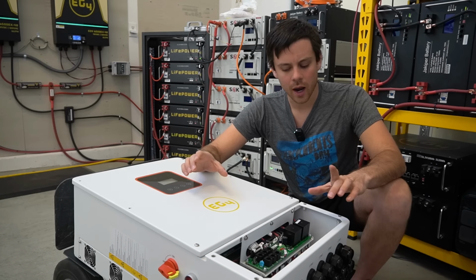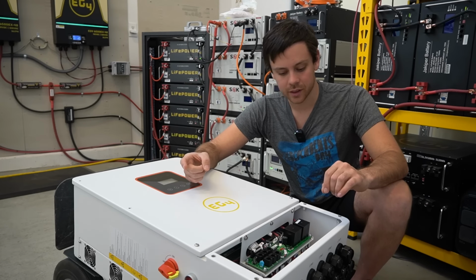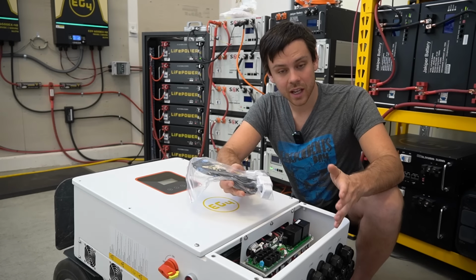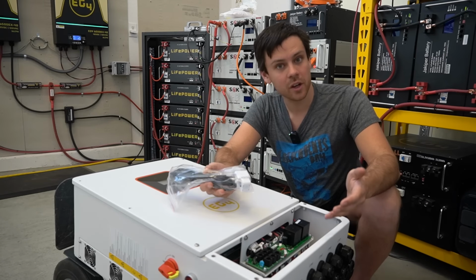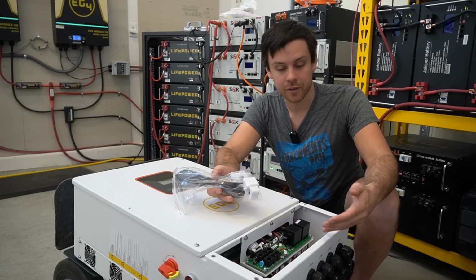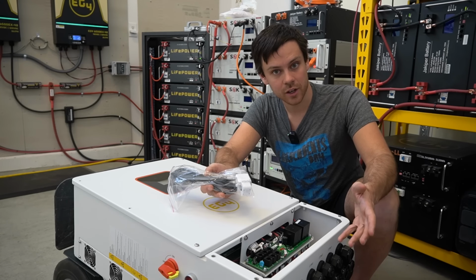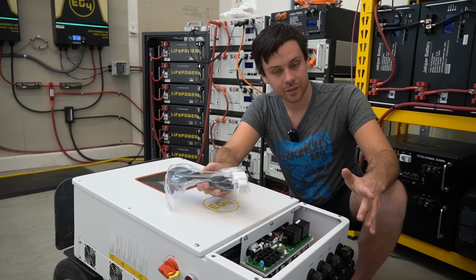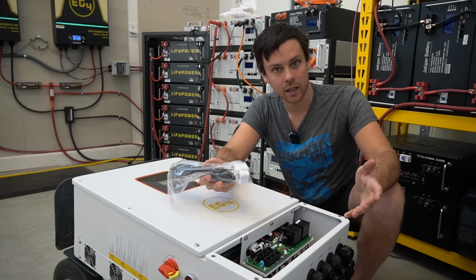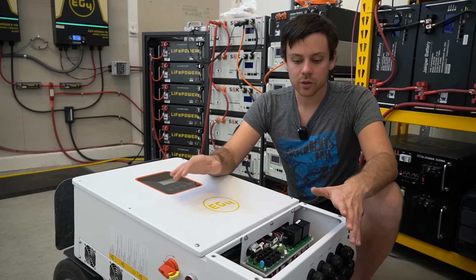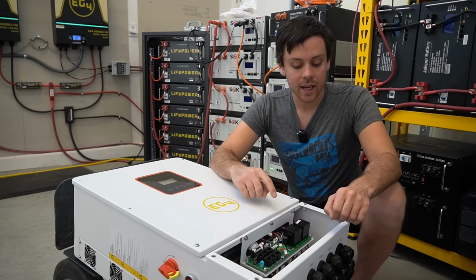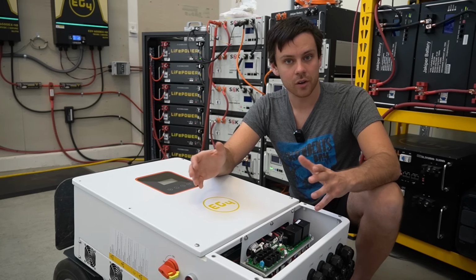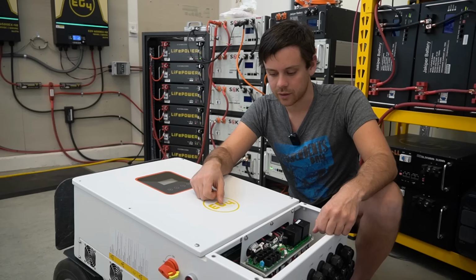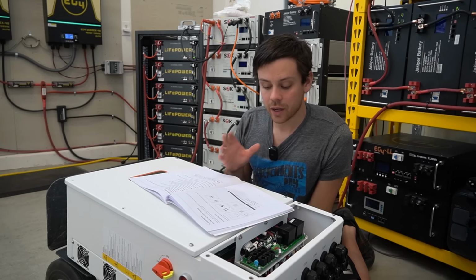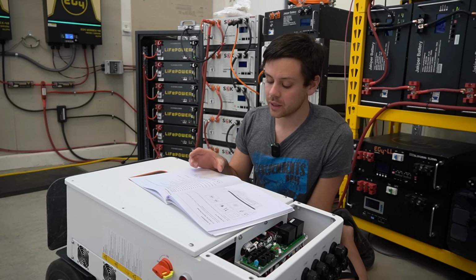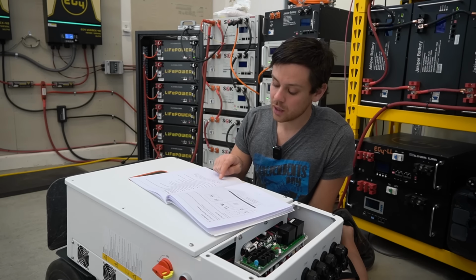And these features make it a true hybrid inverter. You can either use it as an AC coupled system with CTs that actually come with the unit and offset your loads without backfeeding the grid, or if you have an agreement with your utility and you have net metering, or if you get credits, you can use this to take the excess generation that you produce and legally backfeed the grid. And they have to be certified to do so, and you have to pass inspection and get permits. But this can actually do that. Or you can use it strictly as an off-grid inverter, and you can use the AC input only for the AC charger, like other all-in-one systems. So you don't need to use these grid interactive features at all, but you can if you wish to do so. Now, even though this is waterproof, I was reading the manual this morning, and they do not recommend to have this unit in direct sunlight and with rain exposure.